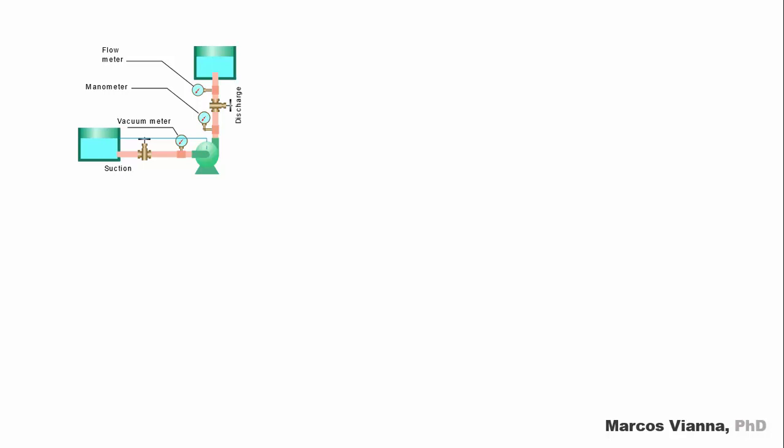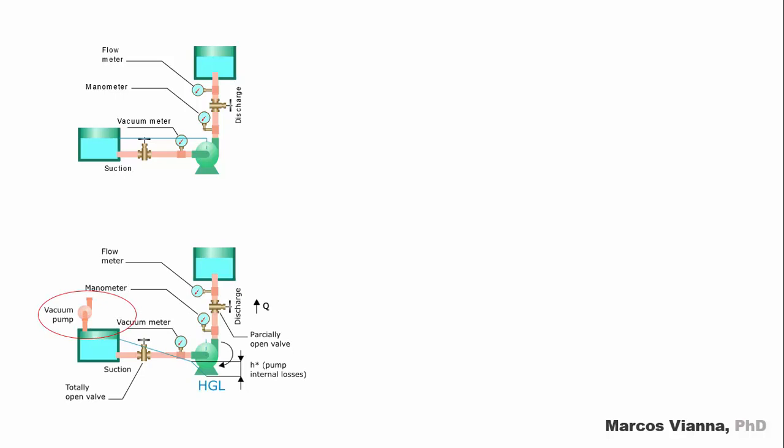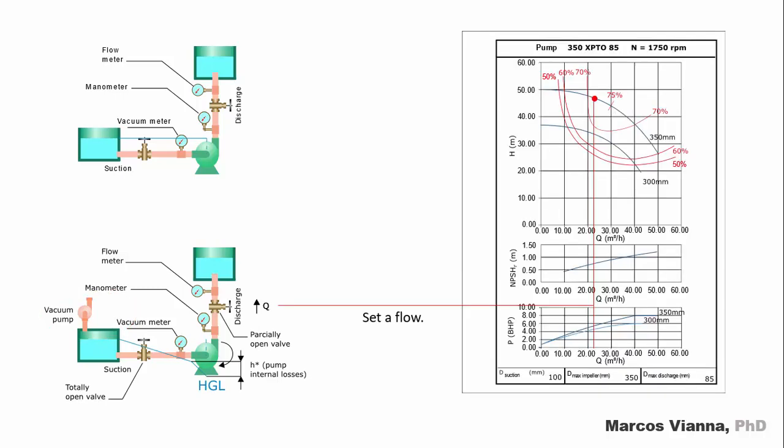Let's see how the manufacturers find the minimum positive suction head that the pump requires to avoid cavitation. This is our traditional installation for running pumping tests. We'll make a modification. Let's put a cover on the suction sump and install a vacuum pump on it. Let's begin our tests.